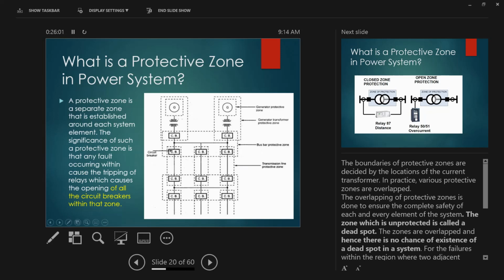In the generator, it has its own zone. It doesn't care about the other protection, the transformer. It only cares about the protection of the generator, which is a different animal of protection relay. And if you are looking at the transmission line, you have line differential, all this stuff. And here again on the low voltage. If you look at them, everything is covered. That's how they design it.